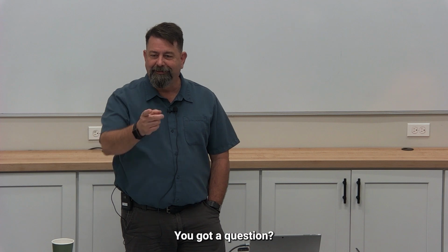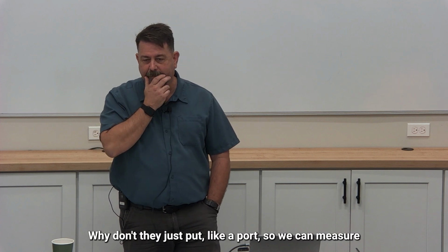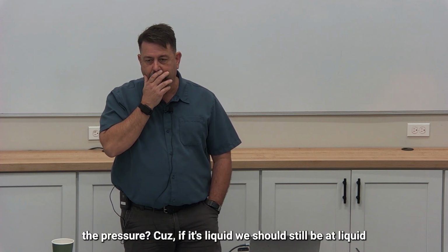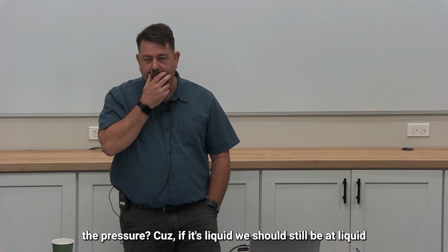I see you pointing a finger, Chad. You got a question? Julie? Why don't they just put a port so we can measure the pressure? Because if it's liquid, we should still be at liquid pressure, should we not? So, no, we will have a pressure drop through the TXV. It'll be a pressure drop, but it'll still be. Yep, we have to calculate superheat to know it.